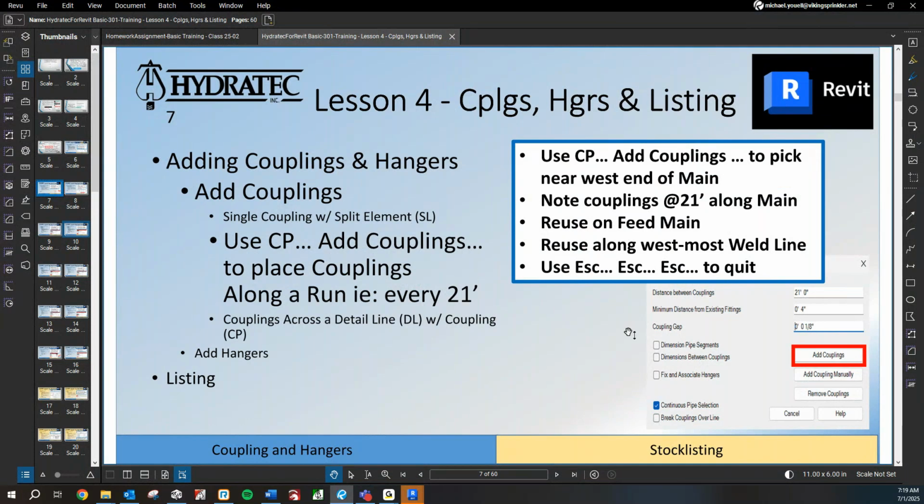That's knuckle room. You can't put a coupling right at a pipelet. You can't really put it 1 inch away from a pipelet. 4 inches is probably a minimum. And if there's a really long run of pipe, the little gap between the ends of the pipe where you put the coupling kind of gangs up on you. If you had 160 feet of pipe, you'd have 8 couplings, and if each coupling gave you an extra eighth of an inch, your overall length wouldn't be 160, it would be 160 foot one. So we account for that by putting that gap in there.